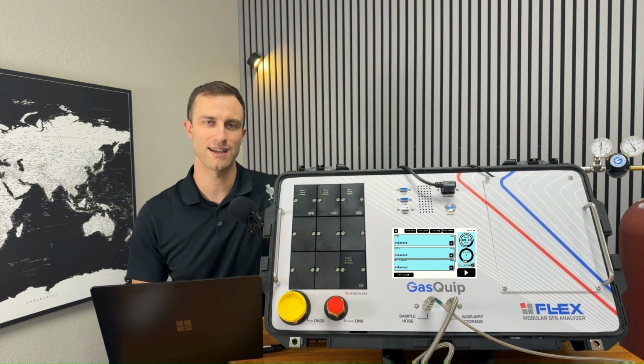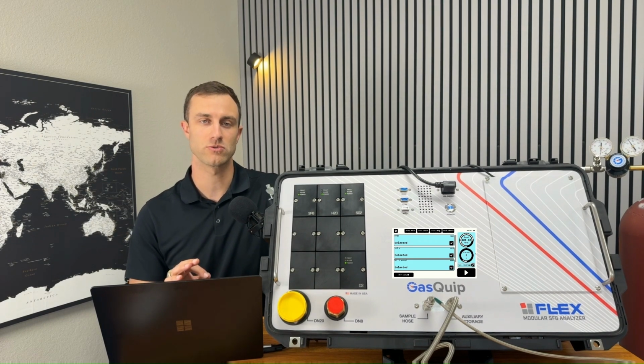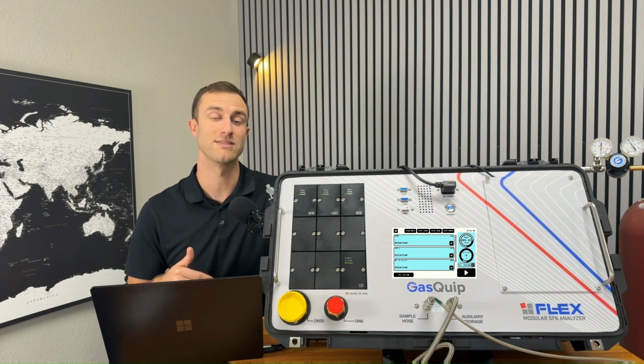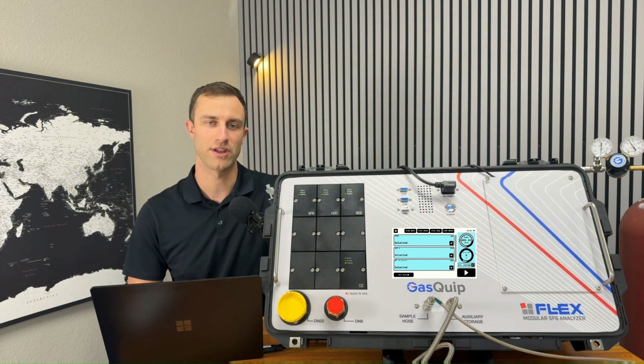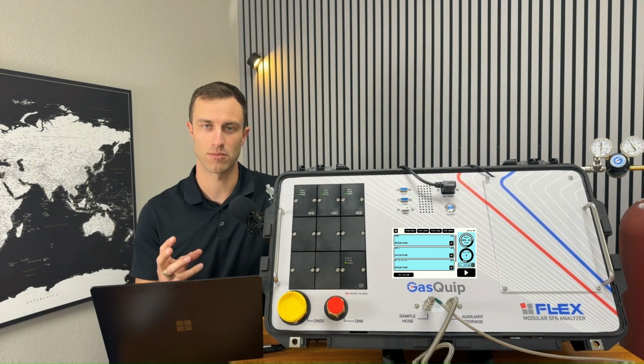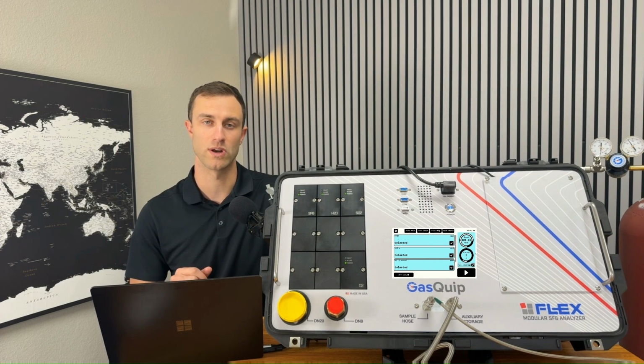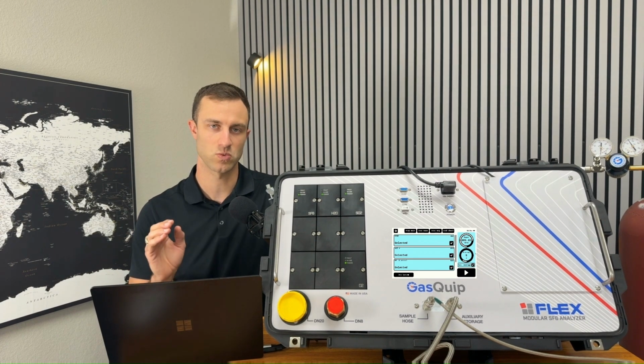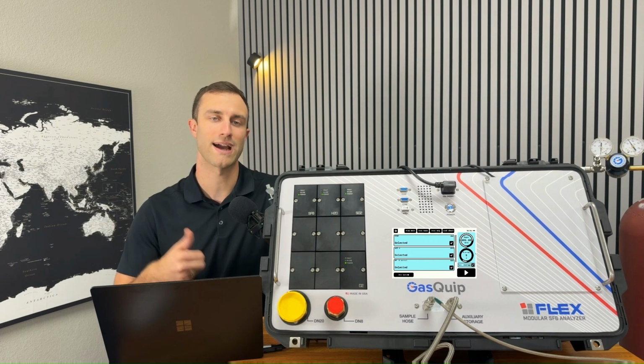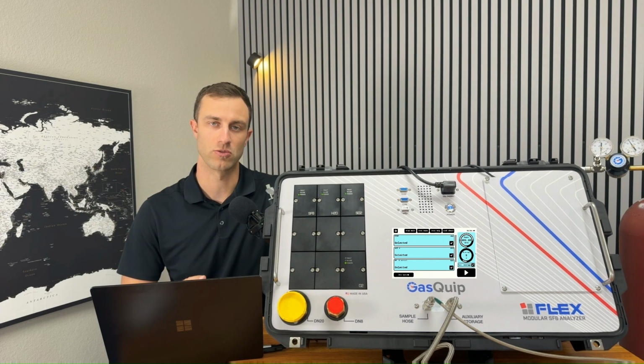Also, if you are testing a gas breaker and you pump back into that gas breaker, you can expect your moisture results to be a lot higher on any subsequent tests. You have to allow the gas to re-homogenize inside the breaker for at least 24 hours if you want to get a good representative result from that breaker again. So if you test, and then test again, but you pump back into that breaker, you're not going to get a good reading on your moisture. It's going to be skewed higher than it actually is inside the breaker.